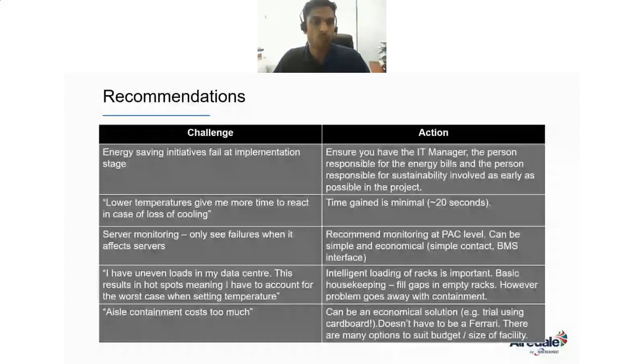Next point, I have uneven loads in my data center, so the probability of hotspots is high, so the worst case needs to be accounted for. For that, it's a basic question of housekeeping. Basically, we have to load the racks intelligently and fill all the gaps. However, the problems can be mitigated with containment as well.